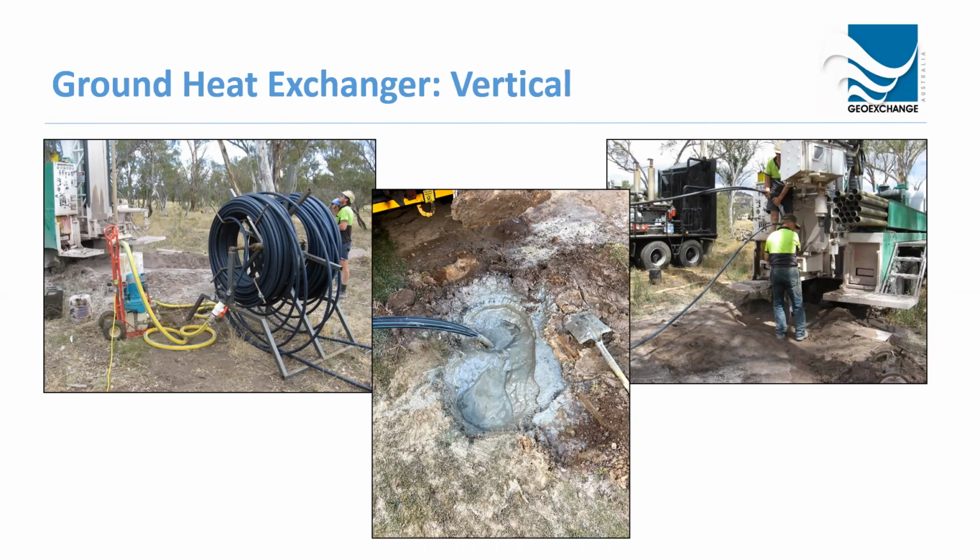Obviously, every now and then, I've had once or twice, we've seen a loop turn up to site and a forklift or something's punched a hole in it. Pretty rare, but you're still checking the integrity of it in that respect, making sure there's no leak or anything in the system. We don't want any other joins in that system. We just want that single one at the bottom. You can get some factory fitted join systems. Some of the crosslink poly pipes will actually pretty much have a bend in them themselves, or you can put the fitting on yourself on site. So it just really depends on how you want to do that.